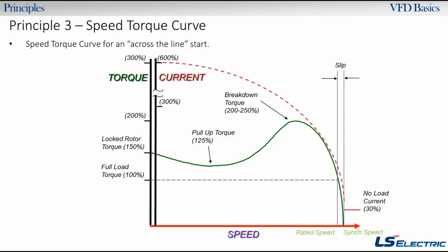But let's just look at this a little bit more. So initially you have your 600% current. You're going to have a locked rotor torque because that motor is locked up. It's going from a stop. So it's going to take some time to get up to speed, which is this bottom horizontal line right here. Okay. So as time goes on, a very short amount of time, you're going to hit this pull-up torque where your torque starts increasing. And then you hit this breakdown torque, which is the maximum torque that motor could possibly put out. Okay. And then eventually you're going to hit your rated speed.